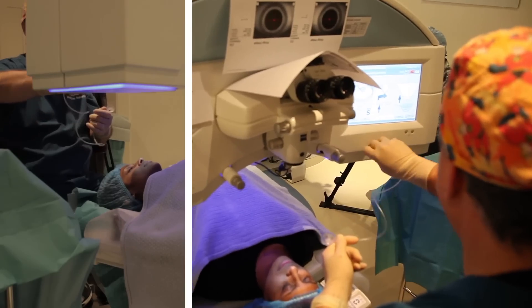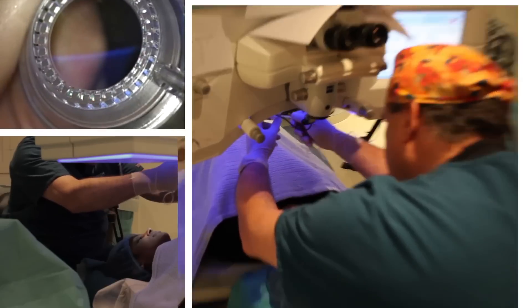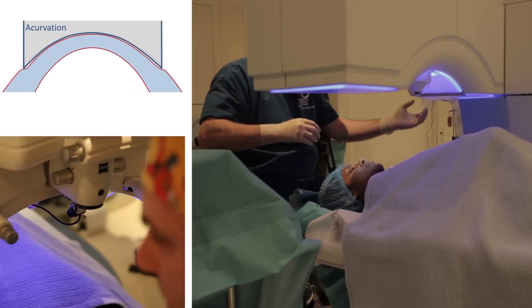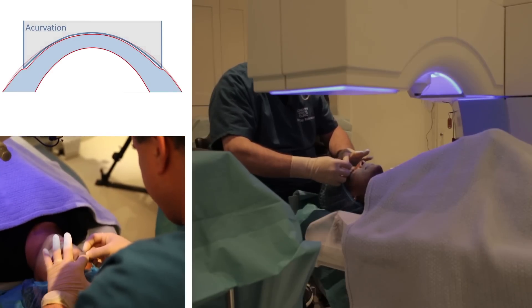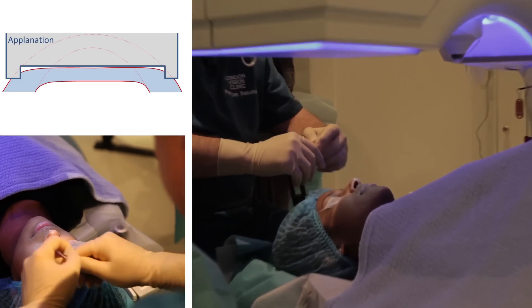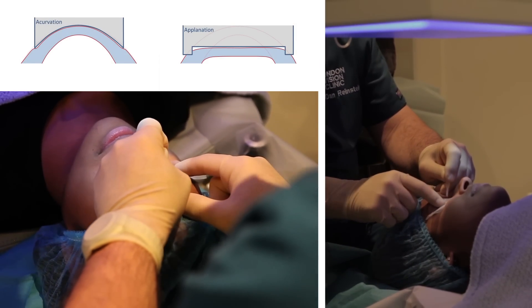The corneal contact glass is vacuum secured to the optical delivery cone aperture. The VisuMax coupling contact glass interface is specifically curved to minimize the corneal distortion produced by classical flat applanation. The coupling produces accurvation rather than applanation.